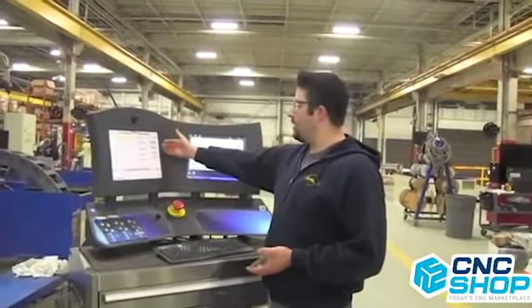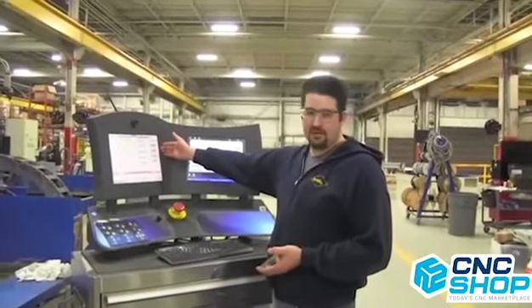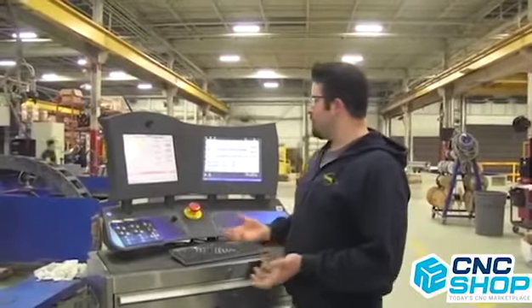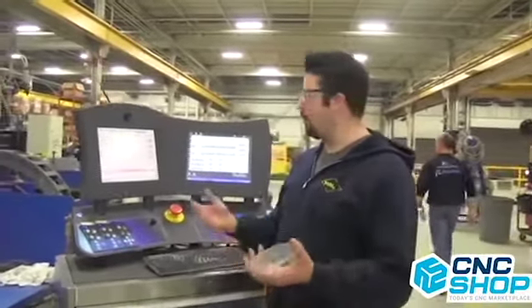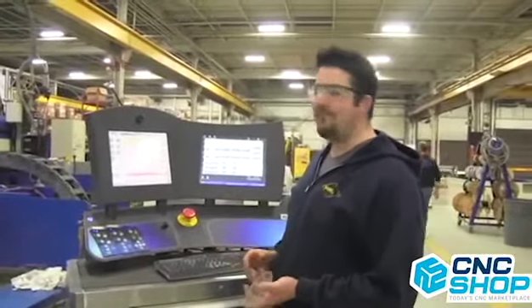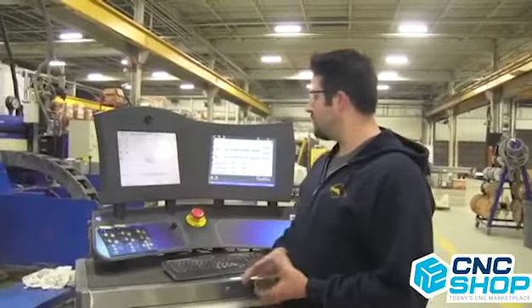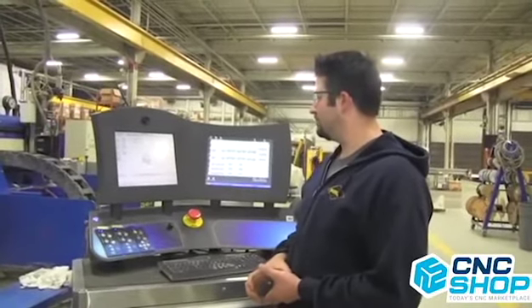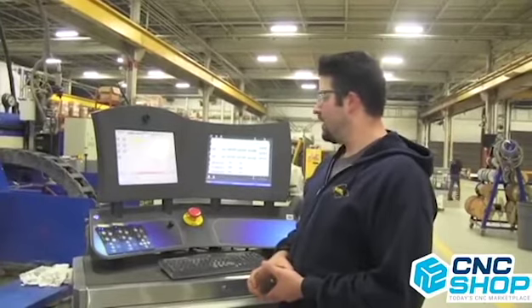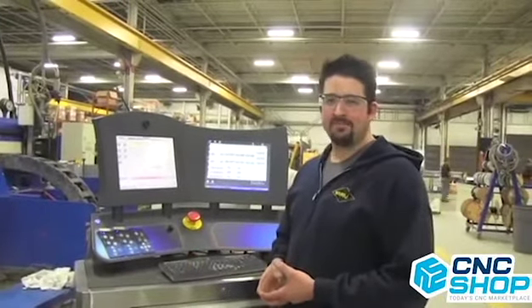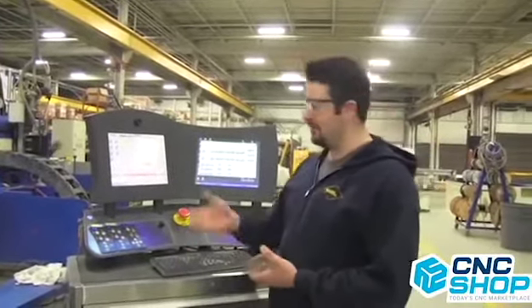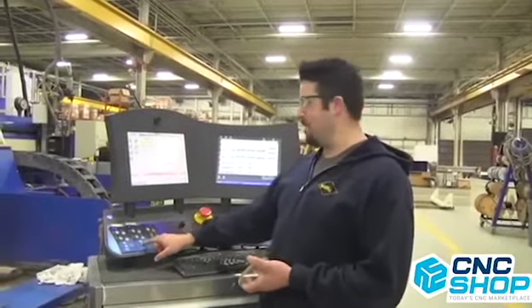And if I look again, what I'll find is that my height sensor target will change. Once my height sensor target has changed from whatever it was before, I can click the Save button. And now my height sensor is calibrated. That's a pretty simple process, so all I need to do to check it is turn on my height sensor.